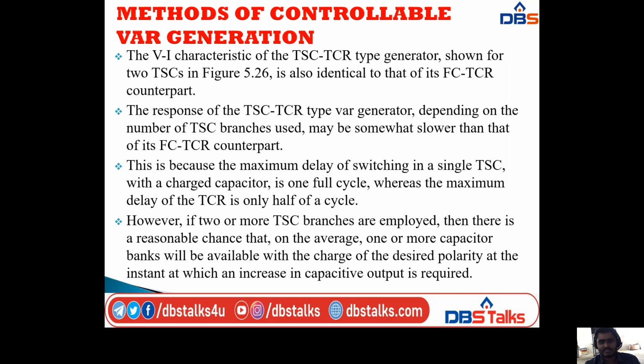Here the response of the TSC-TCR VAR generator, depending on the number of TSC branches used, may be somewhat slower than that of its FC-TCR counterpart. This is because the maximum delay of switching in a single TSC with a charged capacitor is one full cycle, whereas the maximum delay of the TCR is only half of a cycle. Understand this one? The maximum delay of switching in a single TSC is one full cycle, whereas the maximum delay of TCR is only half of the cycle.